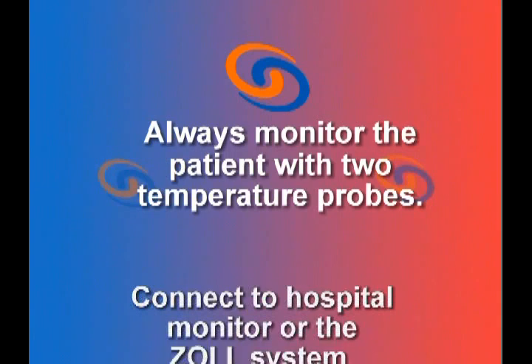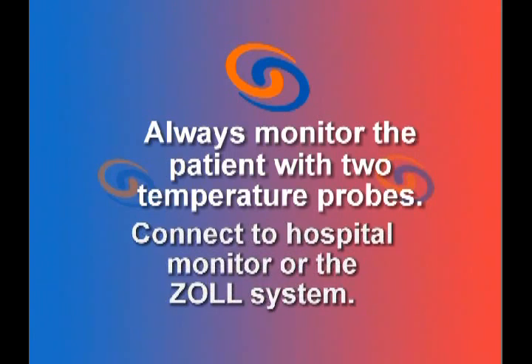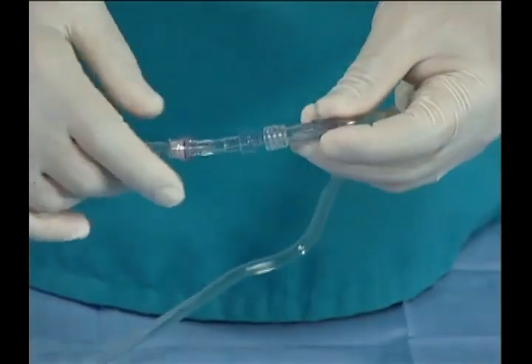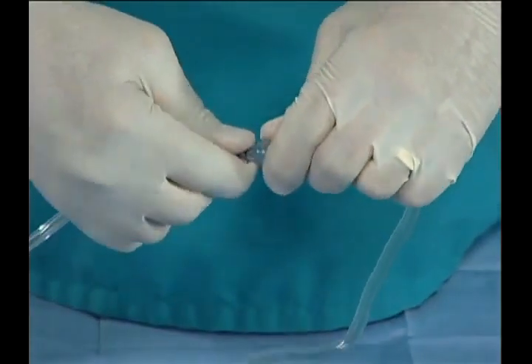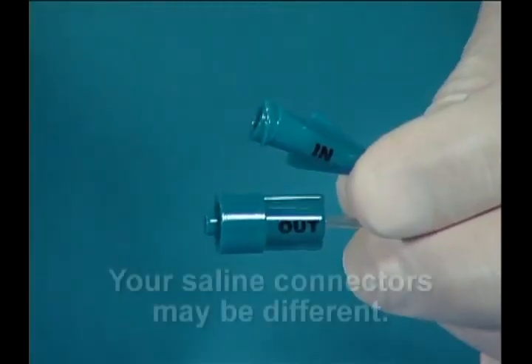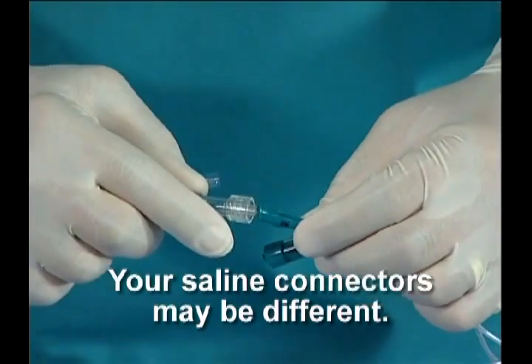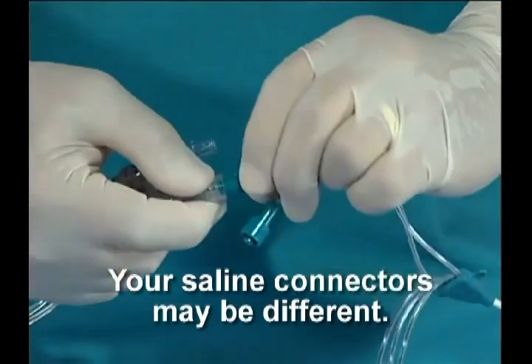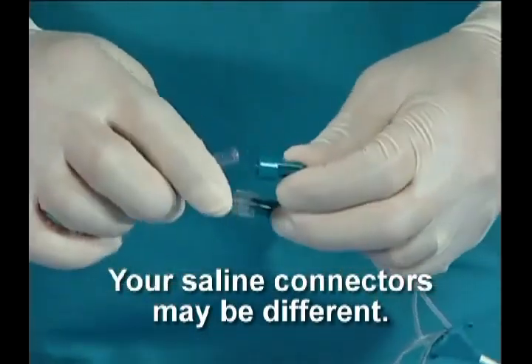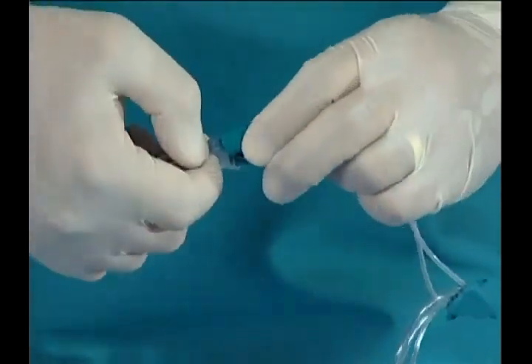Connect the second probe to either a hospital bedside monitor or the system, depending on your hospital protocol. Using aseptic technique, disconnect the supply and return connectors of the tubing and connect them to the saline in and out luers of the catheter. These luer connectors are keyed, making it impossible to connect them incorrectly.